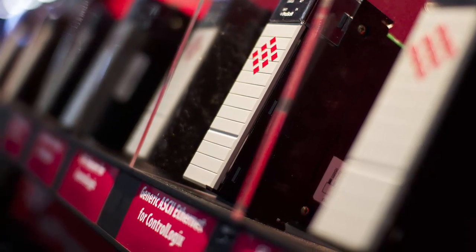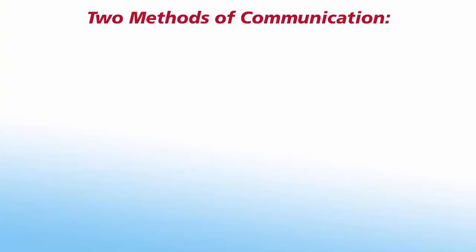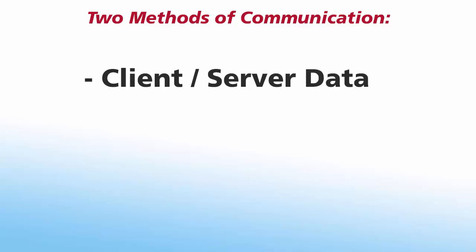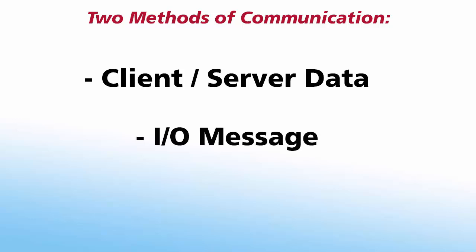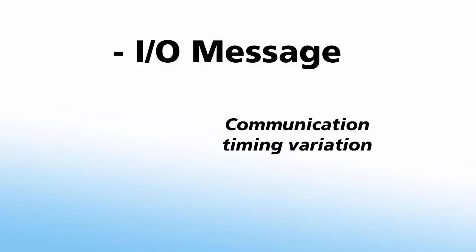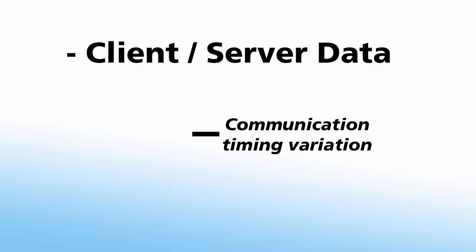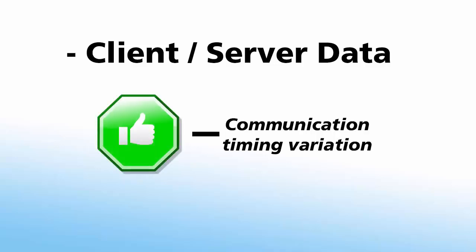We'll begin by defining what the different methods are. Most industrial automation protocols have two methods of communication: client-server data communications and input-output message communications. Each of these methods has its own properties and characteristics that make them suitable for different applications. Both are used to read and write data between devices. I/O messaging is used when communication timing variations are not acceptable, while client-server data communications are used when some variation in communications is tolerable.